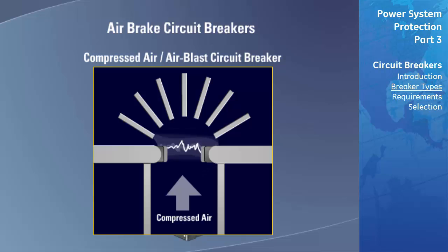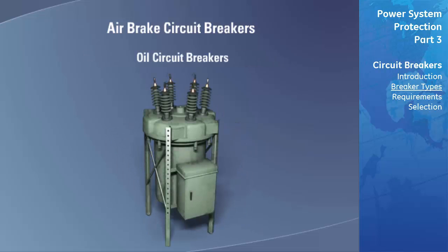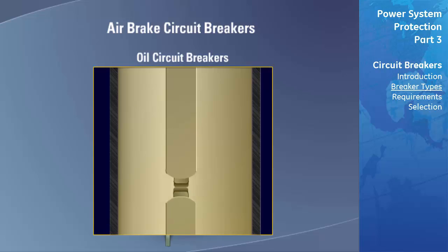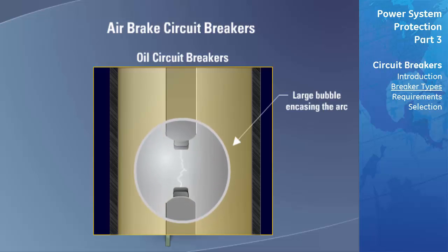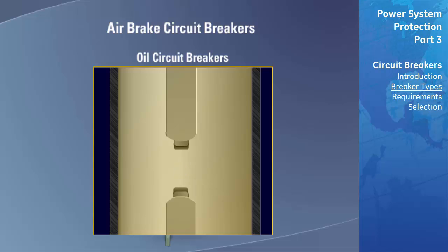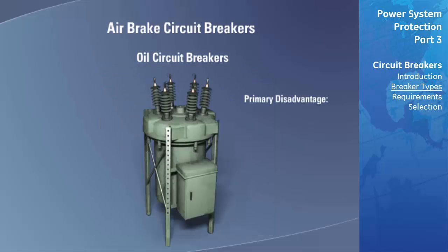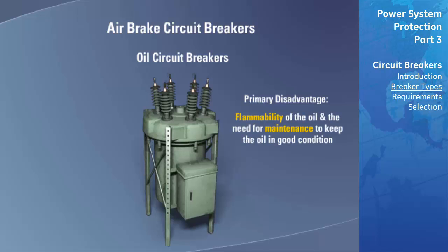Oil circuit breakers function by drawing the arc under oil, thereby extinguishing it. When the electric arc is drawn under oil, it vaporizes the oil and creates a large bubble surrounding the arc. The gas inside the bubble is predominantly hydrogen, which impairs ionization. The decomposition of oil into gas requires energy from the arc's heat, while the surrounding oil conducts heat away, contributing to deionization. The primary disadvantage of oil circuit breakers is the flammability of the oil and the maintenance required.